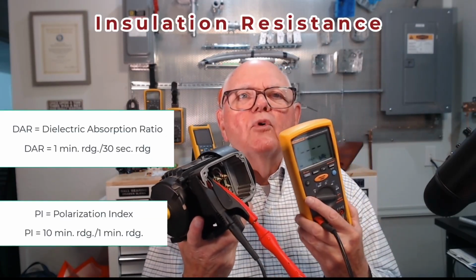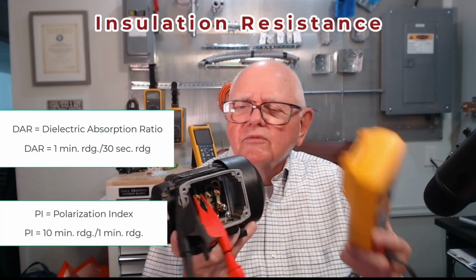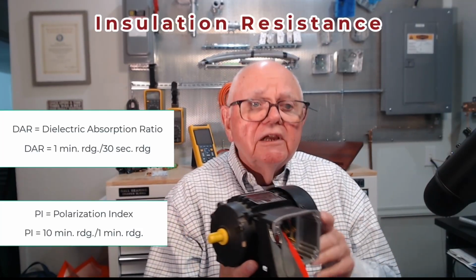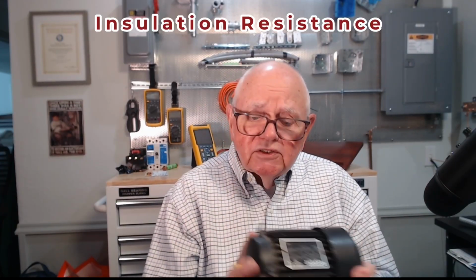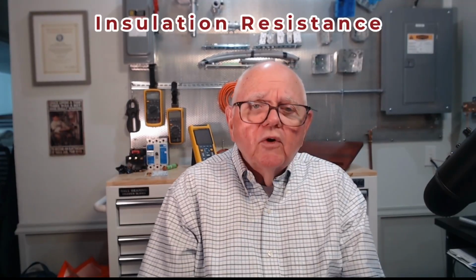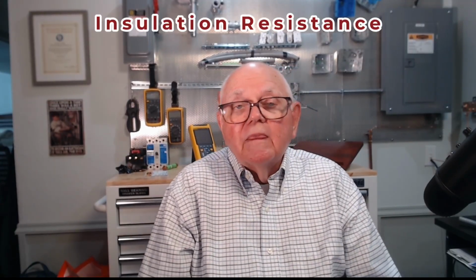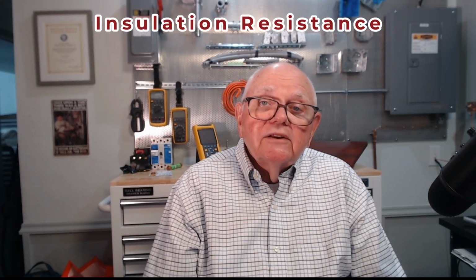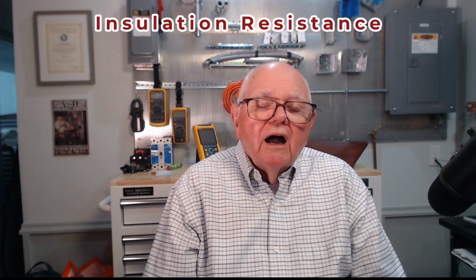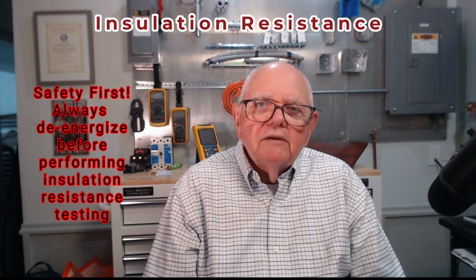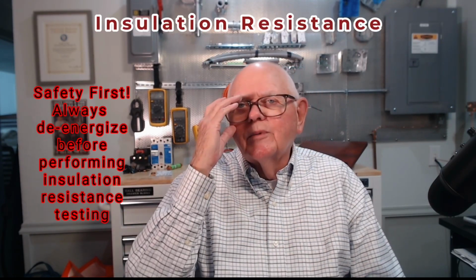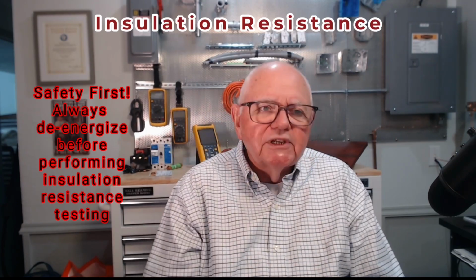I can use that for more advanced troubleshooting when it comes to insulation resistance testing. So, know your insulation resistance tester, know the equipment that you're going to test, right? Make sure that you're trained on that process and know how to do it. Obviously, safety is number one. We're going to de-energize any equipment before we do any insulation resistance testing on it.